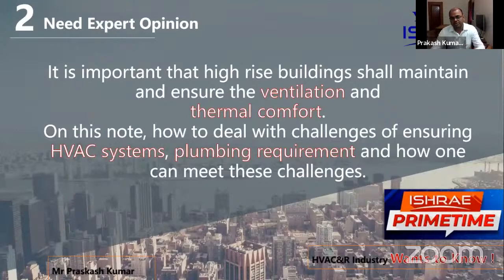What happens is that once air is circulated again and again, people start getting some discomfort in the room, saying there is a lack of fresh air. And in a glass covered building, we have to ensure that fresh air reaches each AHU. So we provide a supply fan on the roof, and from there a fresh air duct is connected to each AHU unit or AHU room, to ensure that all the occupants of a high-rise building never feel discomfort.